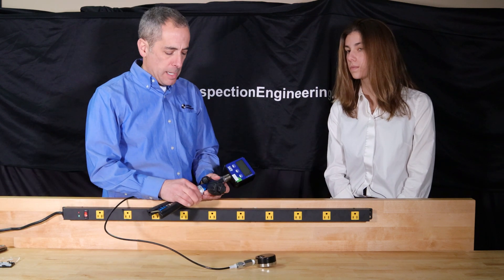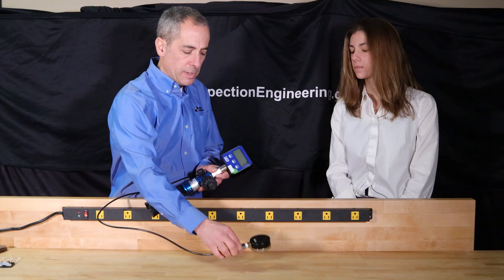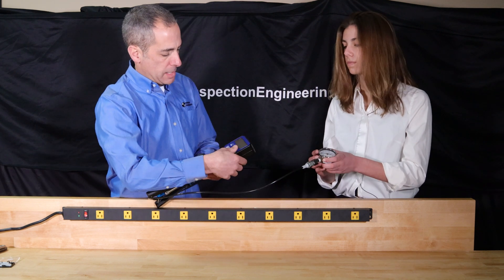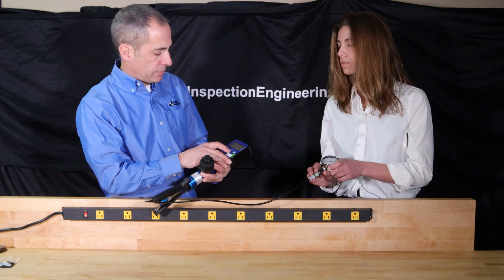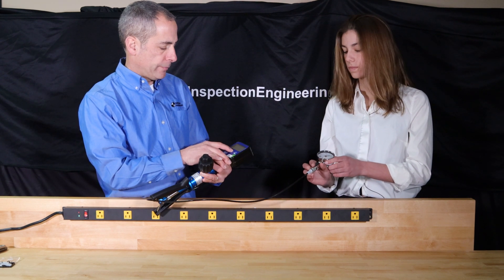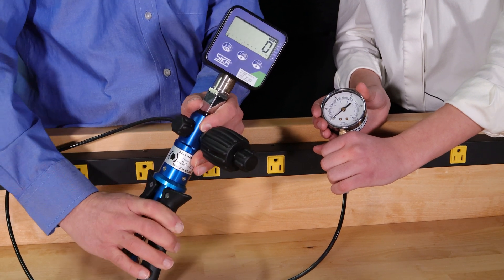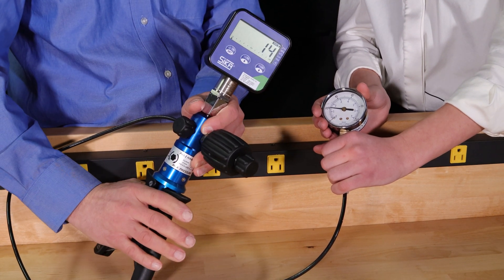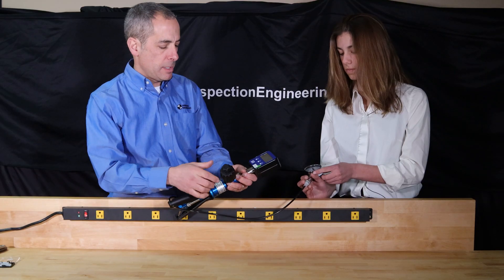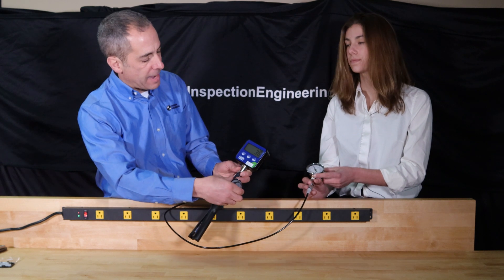To do it, it's actually pretty simple. There is a valve here to close it. Once everything is connected and sealed, it is turned on and I've hit the reset button to zero it. Once I'm at zero, I can begin pumping, and typically people would check it at two different locations. One pump gets me to 37.